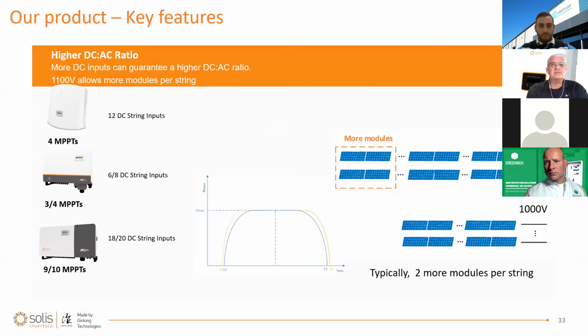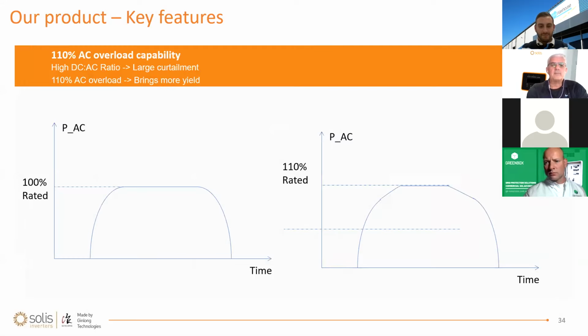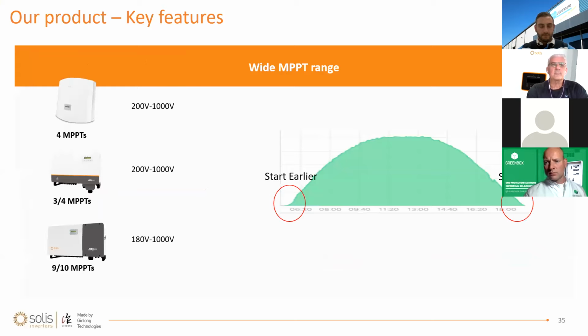Higher DC-AC ratio means you can get obviously more energy produced out of your strings. As you can see here, the AC overload capability allows you to get more energy out of the system that you have for the modules that are supplied. Wider MPPT range obviously starts lower in the morning, shuts off later in the afternoon, which is wonderful. So you can get, again, more energy yield during the day.